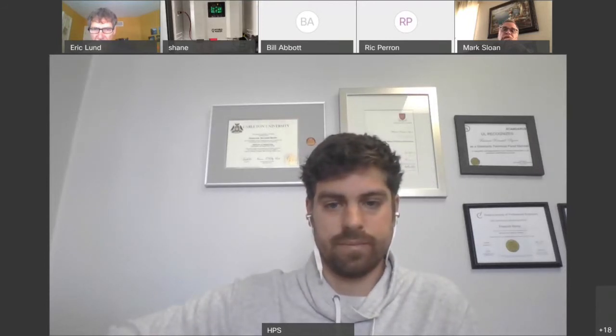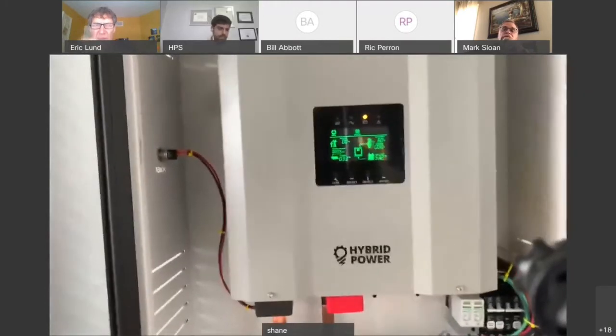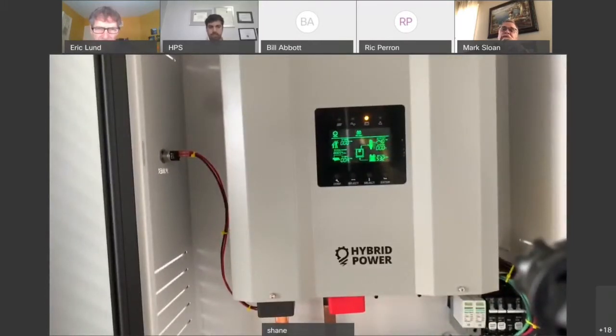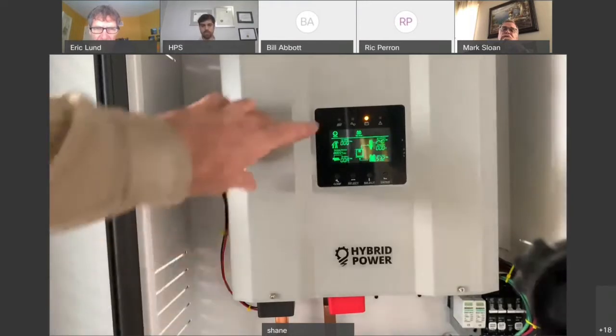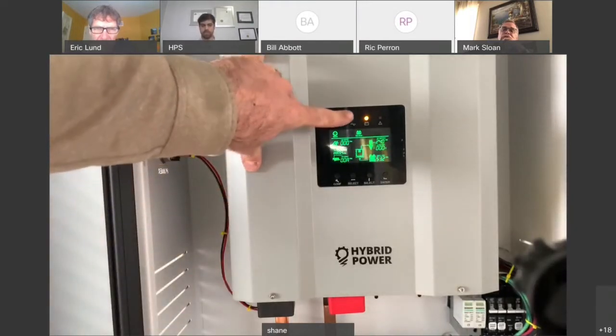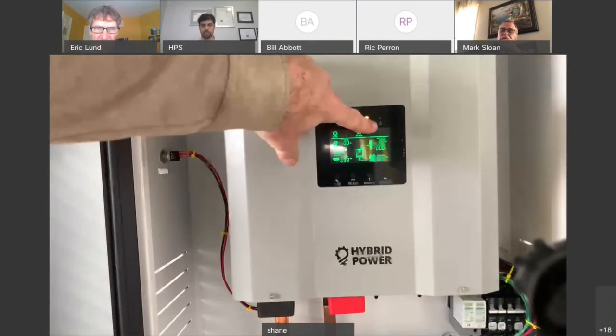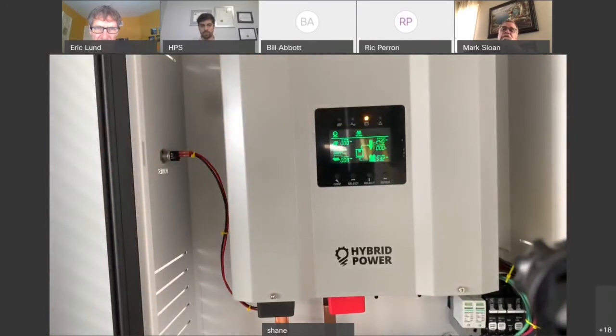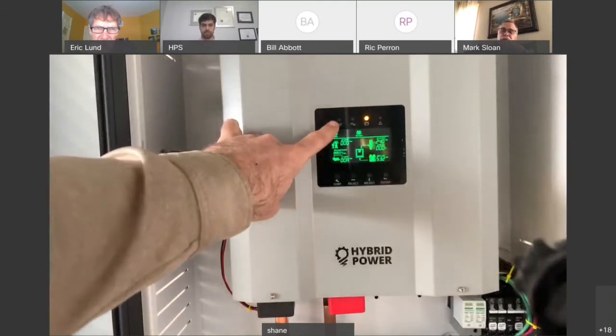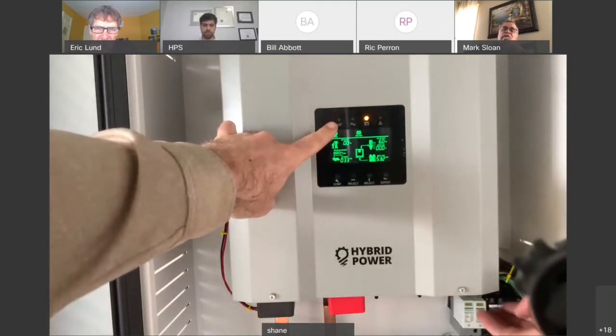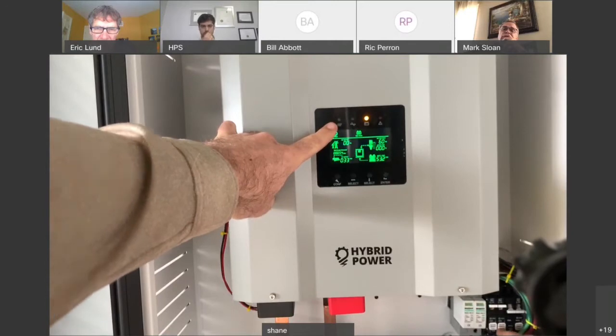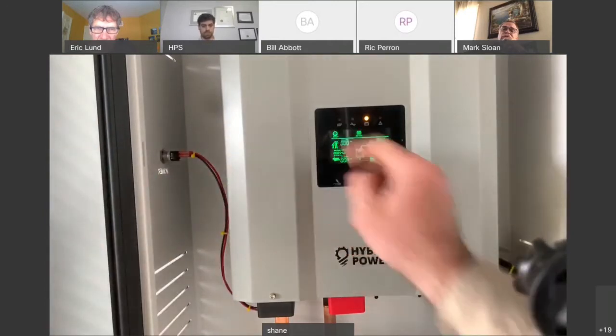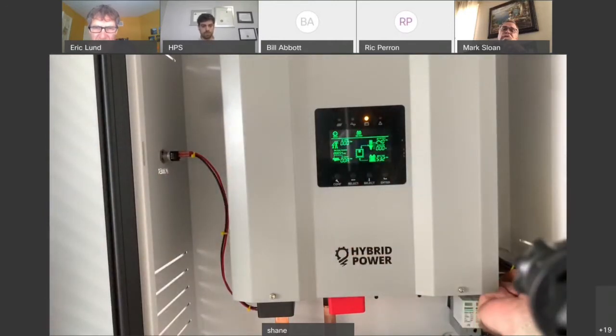Perfect. All right, so on the screen here, it's a very simple screen. There's enough information for the homeowner to understand what's going on, and there's enough information for a troubleshooter to easily identify any little fault that happens. So on the top, we have our PV indicator, our AC indicator, battery indicator, and our little fault sign, right? So right now we have 0 PV coming in because our breakers are off. So I'm going to energize the two inputs, 30 amps. But now we're still not going to get anything because we have to have the 63 amp going through and the ground fault detection.